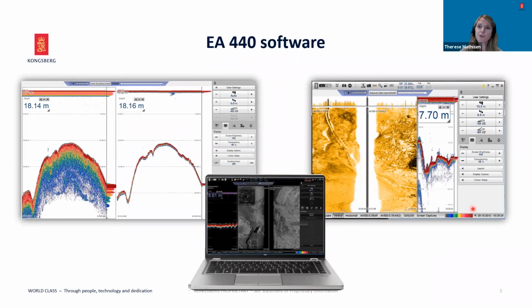The EA440 software is designed to be user-friendly and intuitive. Depending on your requirements, you can set up your views to show the type of data that you are interested in. Data are shown in echograms for each channel. Each channel can be configured separately, such as setting the range which defines start and stop depths of the echogram. You can adjust gain settings and colors to improve the appearance of the echograms, and you can adjust power output settings.